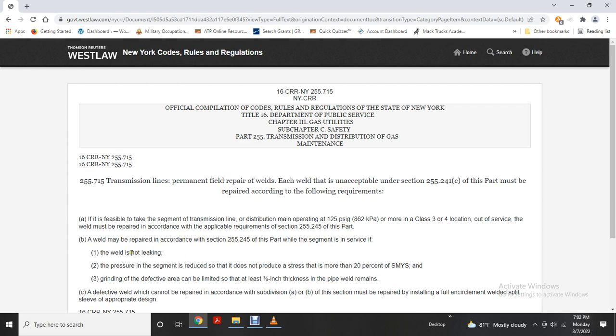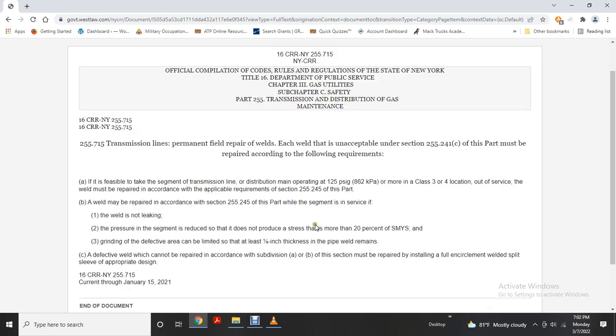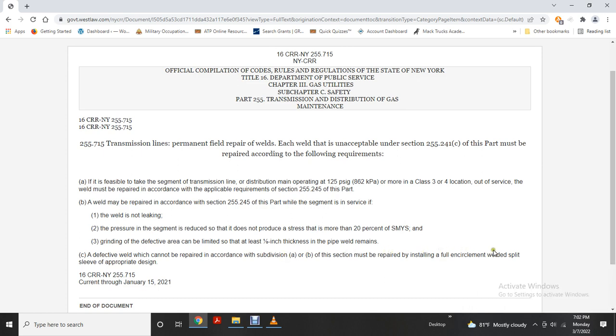A weld may be repaired in accordance with 255.245 of this part while the segment is in service if the weld is not leaking, the pressure in the segment is reduced so that it does not produce a stress greater than 20 percent of the specified minimum yield strength, and grinding of the defective area can be limited so that at least 1/8 inch of the pipe wall thickness remains. A defective weld that cannot be repaired in accordance with these requirements must be repaired by installing a full encirclement welded split sleeve of appropriate design.